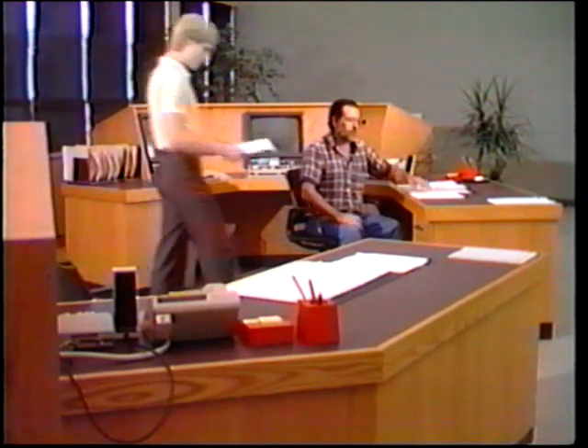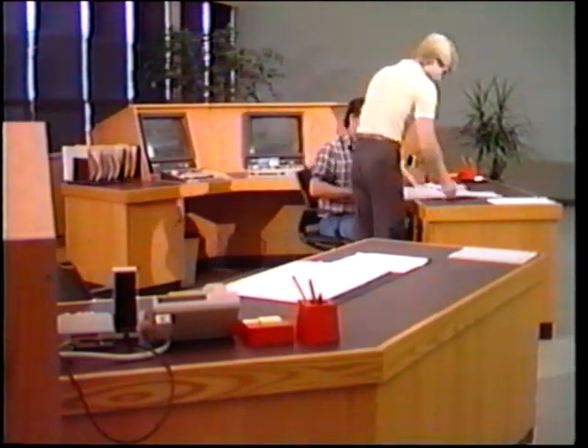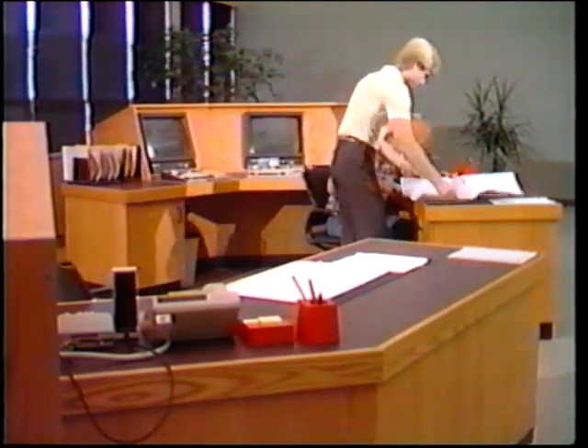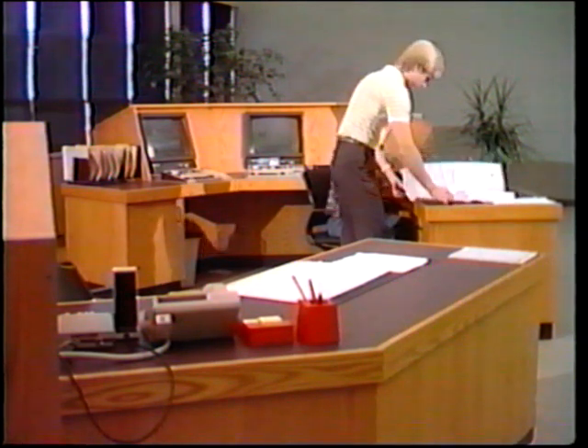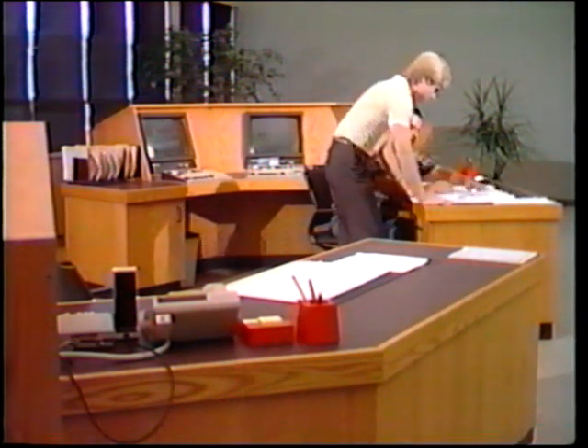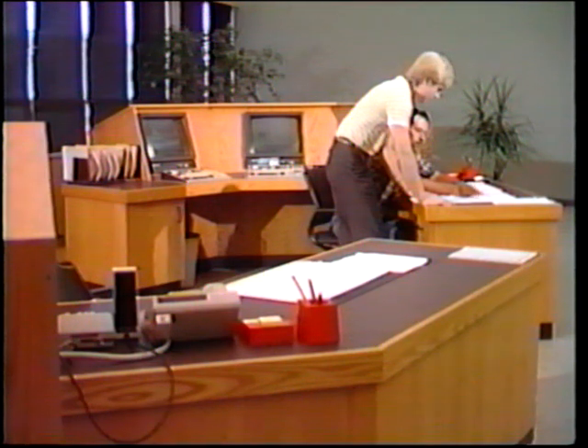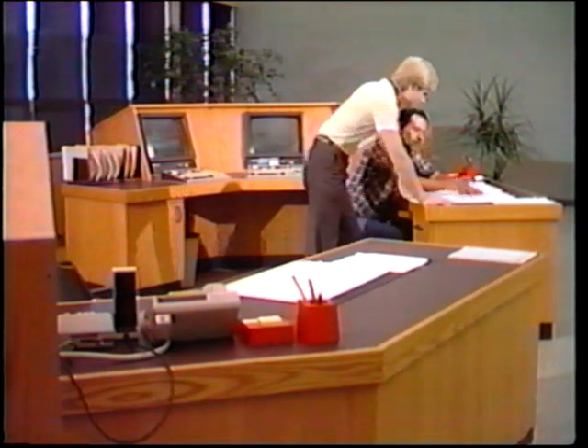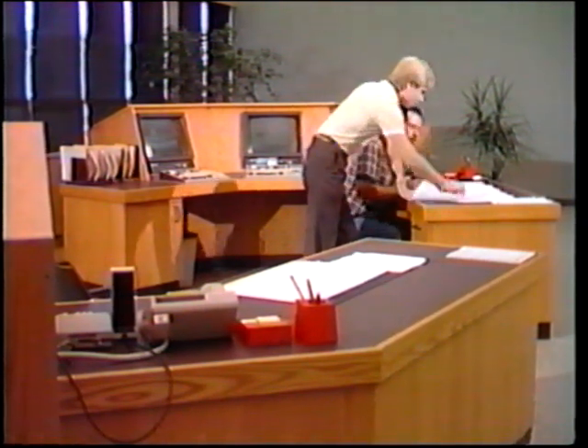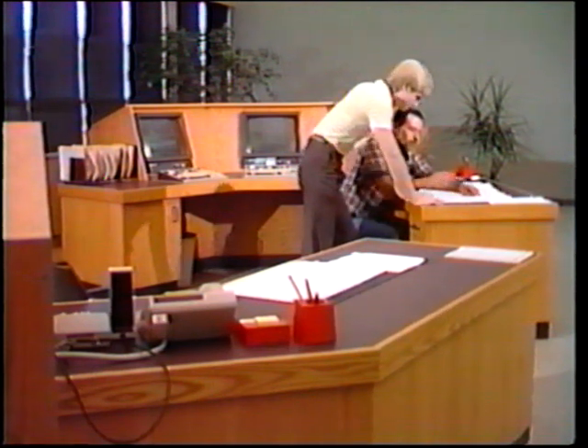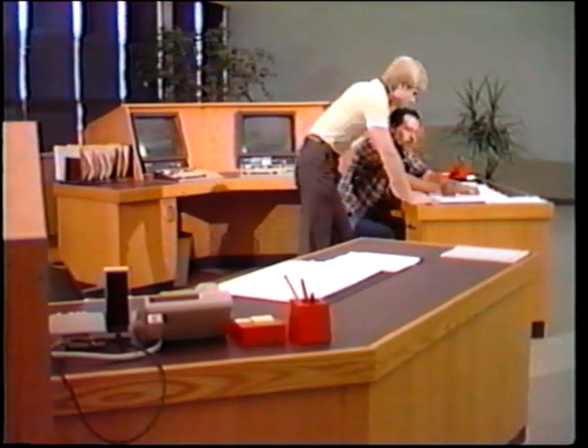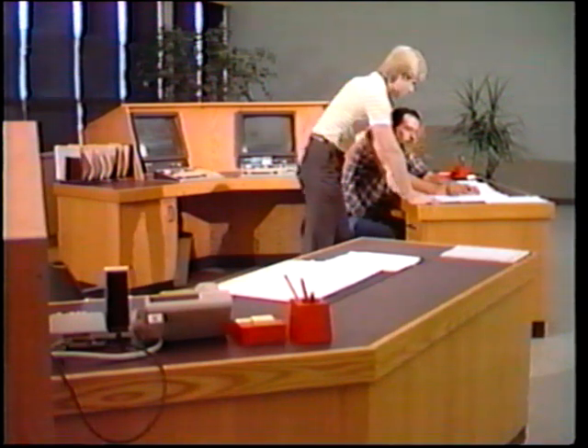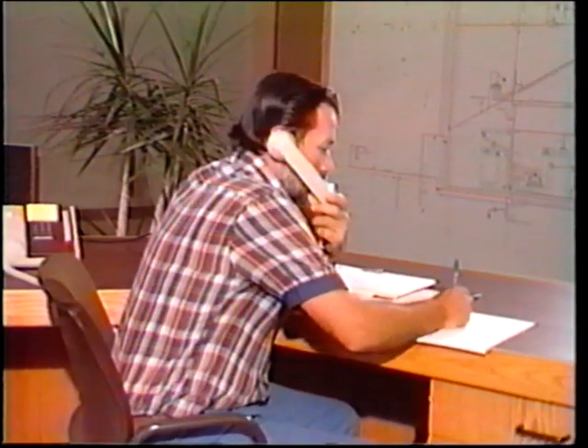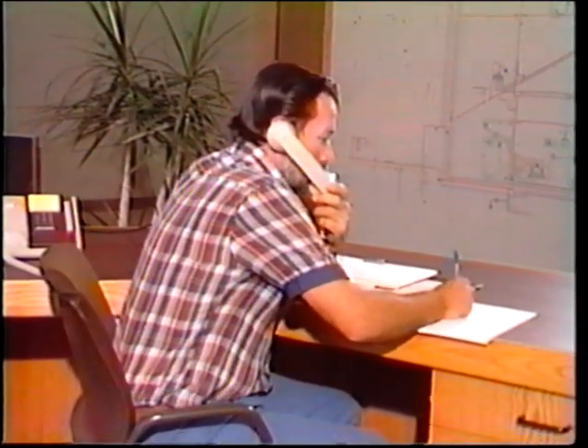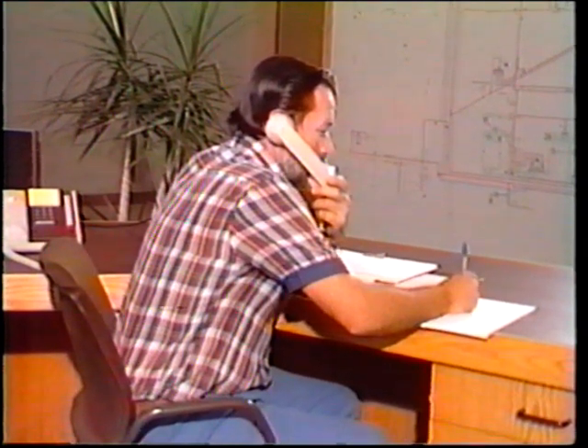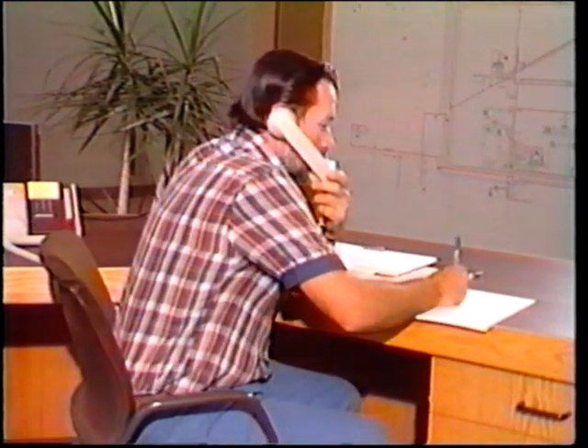Before commencing any tests, the relay technician must discuss the scope of the work to be performed with the operator. They will jointly review the work plan along with the high-voltage operating diagram to determine if the test can be performed safely. The operator should also be alerted to the potential for inadvertent tripping during the in-service tests. This will allow the operator to prepare a contingency plan. He may also wish to inform interconnected neighboring utilities.